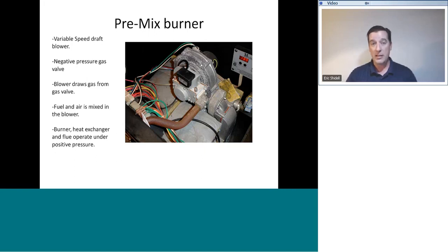Because the blower now is literally blowing into the heat exchanger, and it's going to blow all the way through the heat exchanger and all the way through the vent, both the burner, the heat exchanger, and the flue are now under positive pressure. It's a completely different style of combustion, which is why I said it'll be tricky.